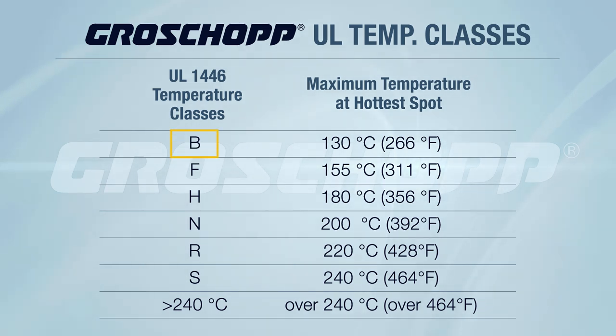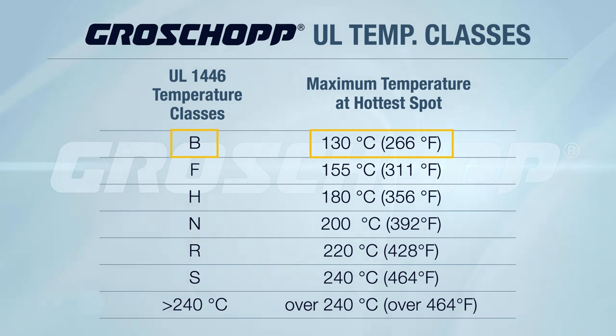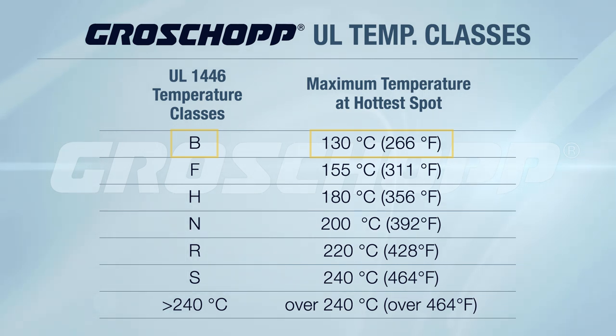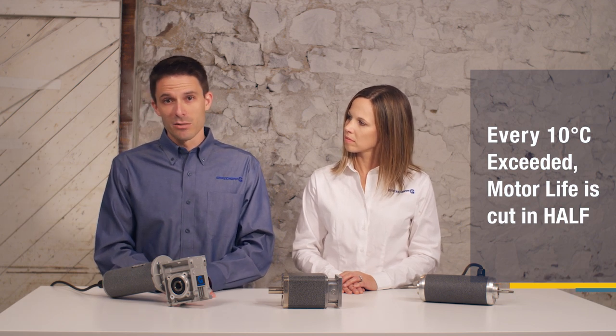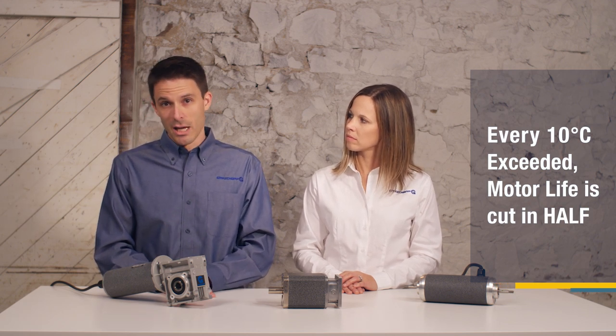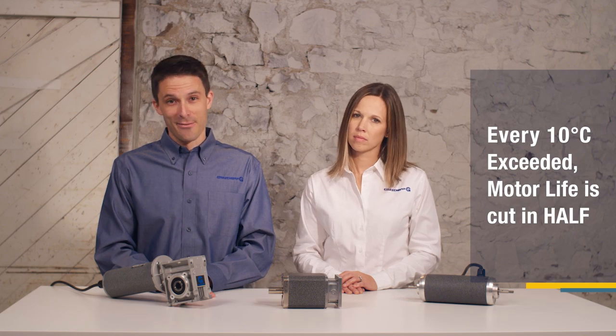For example, temperature class B means that the maximum temperature is 130 degrees Celsius, and that if this temperature is exceeded, the life of the motor will be shortened. This chart helps you determine what level of protection you need for your motor to run in extreme temperatures. Here's a rule of thumb: for every 10 degrees Celsius that your application exceeds the maximum temperature rating, the motor life is cut in half.